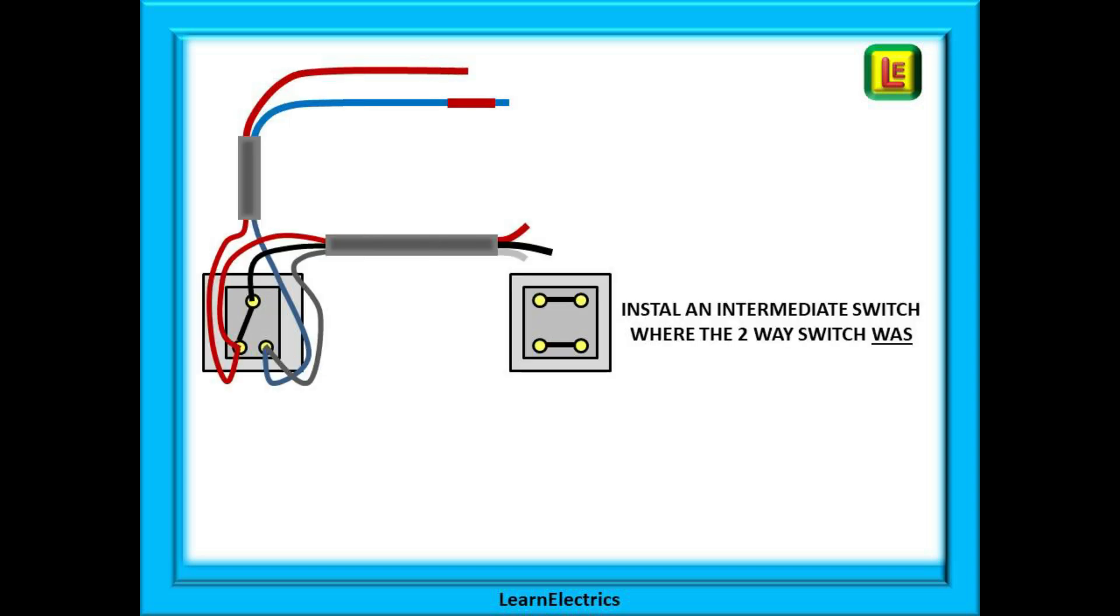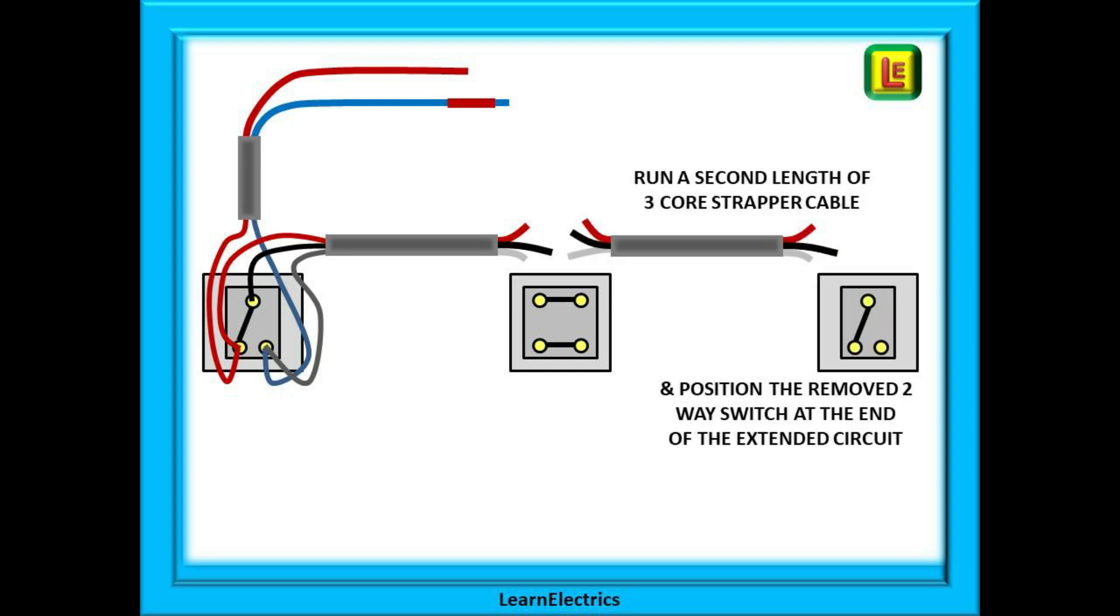Now install the intermediate switch into the space where the removed two-way switch was. Add another three core plus earth strapper wire from this switch to the new switch, in our example the new garage doorway, and position the previously removed two-way switch by the garage door.